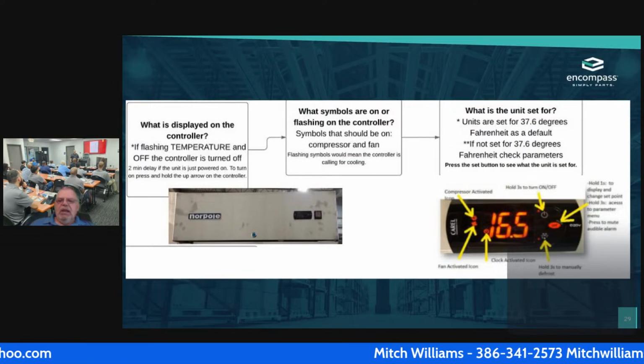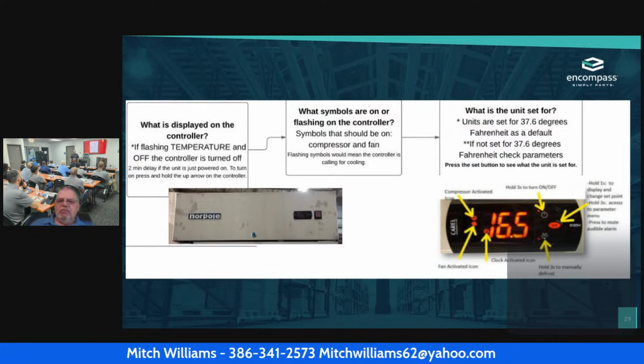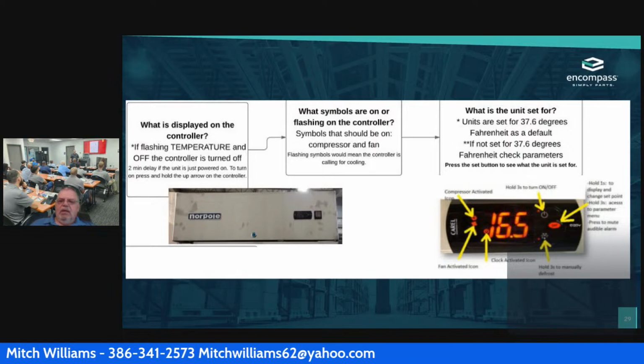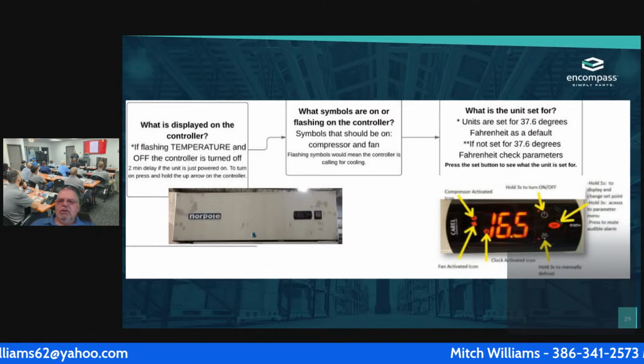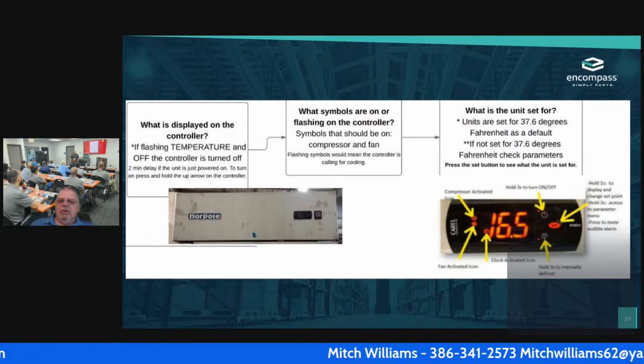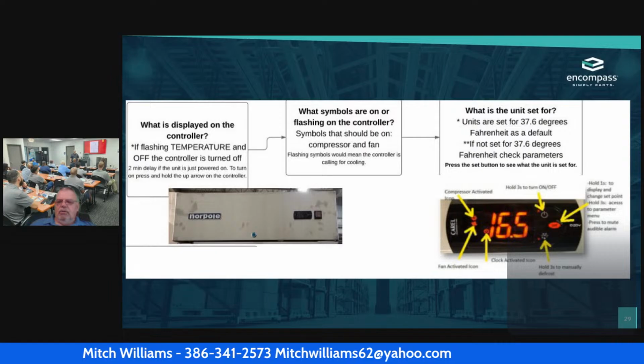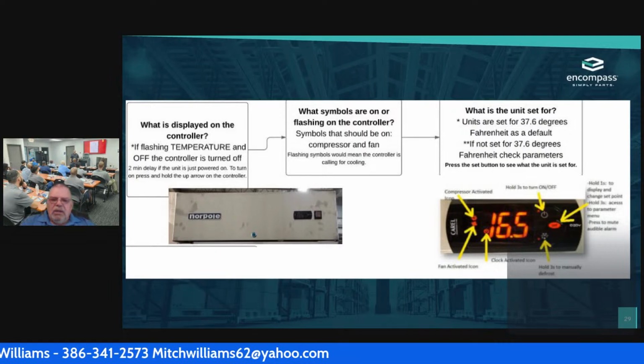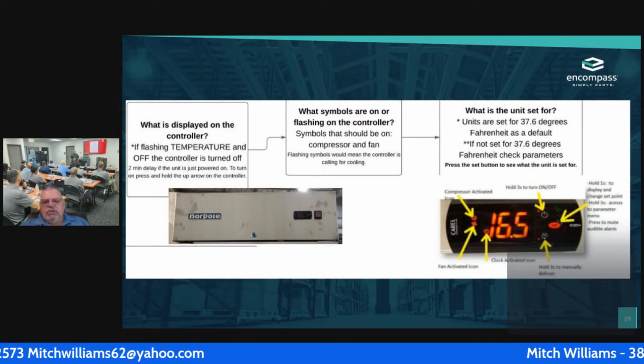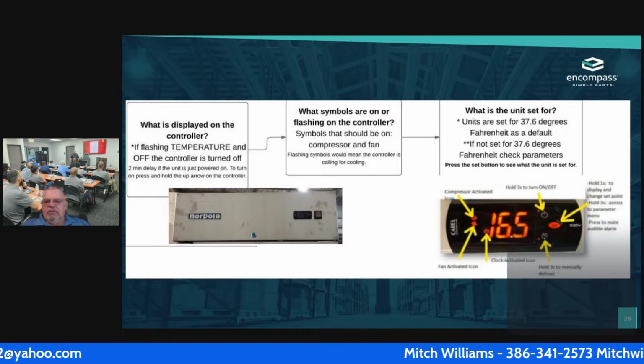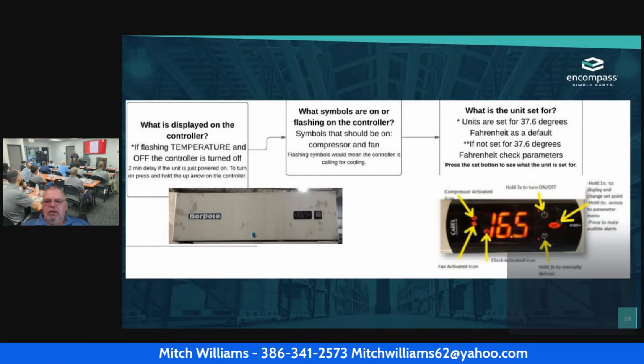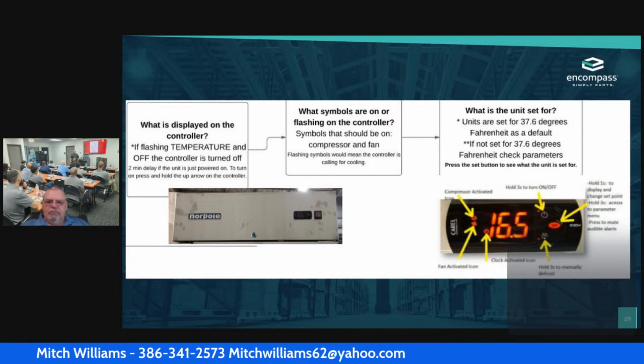What is the unit set for? So the units are set for 37.6 degrees Fahrenheit as a default. If it's not set for 37.6 degrees, check your parameters. Press the set button to see what the unit is set at. That's on that far right side. And if I need to adjust it, of course, I have my up and down arrows that's right there next to the on off.